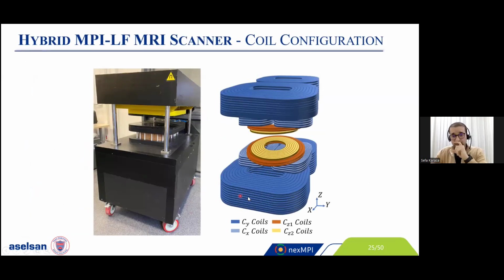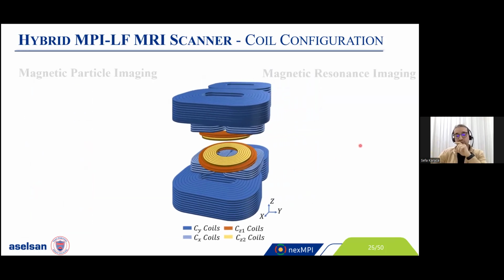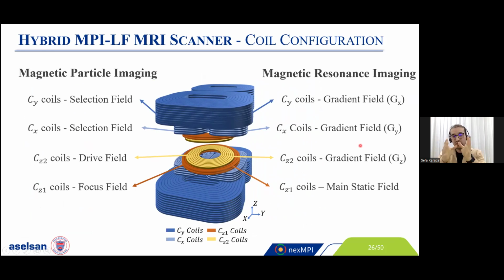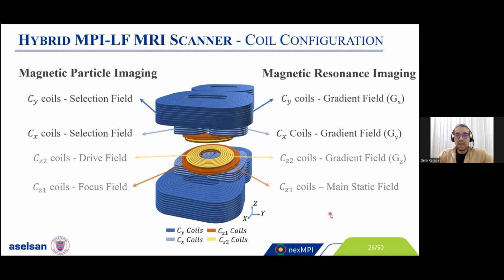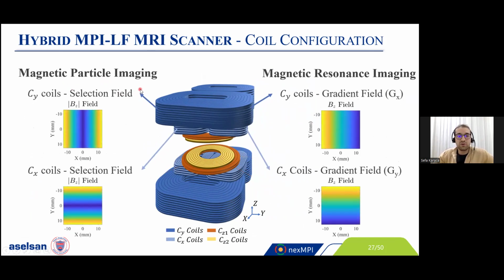So again, this is our system, and this is the coil configuration. You can see 4 different coil groups in here. These 4 coil groups are used interchangeably between MPI and MRI mode, so we are using them in a dual-mode fashion. For the MPI case, as I mentioned before, we generate the selection field by using 2 different biplanar gradient coils called the CY coils and the CX coils. You can see they are the blue ones. Since we generate the gradients in the X and Y direction, we can use them in magnetic resonance imaging to generate the frequency and phase encoding, which provides the spatial encoding for the MRI.